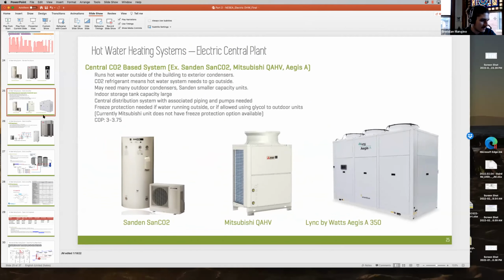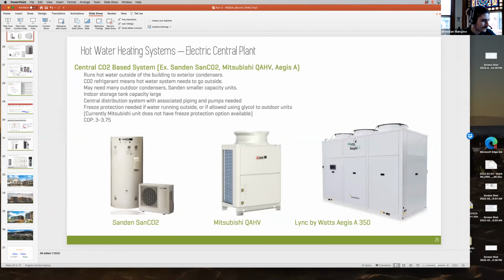So the Watts one is also a CO2. These are the three that I'm aware of that are CO2 based, all single packaged, and you would send the potable water outside the envelope. I believe that's just due to the high operational pressure of the CO2 refrigerant.